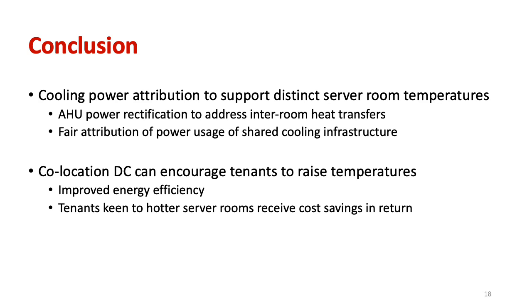To summarize, in this paper, we propose a cooling power attribution scheme to support distinct server room temperatures. Specifically, we rectify the AHU power to address the inter-room heat transfers and attribute the power of the second stage cooling system to the server rooms. With our scheme implemented, the colocation data center can encourage the tenants to raise temperatures for improved energy efficiency. At the same time, the tenants keen to hotter server rooms will be better incentivized because they can receive cost savings in return. This is the end of the presentation.